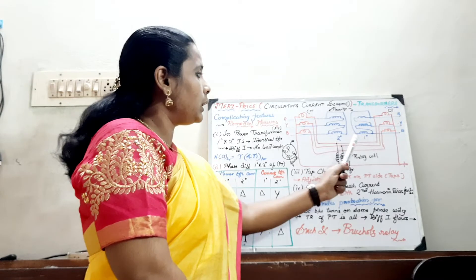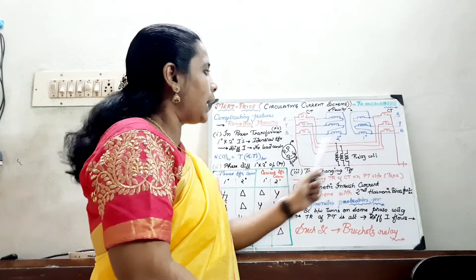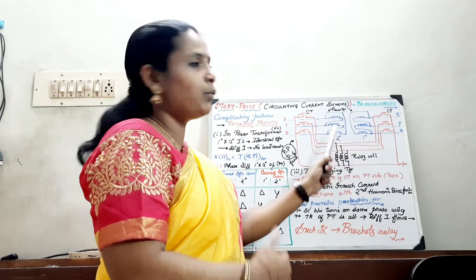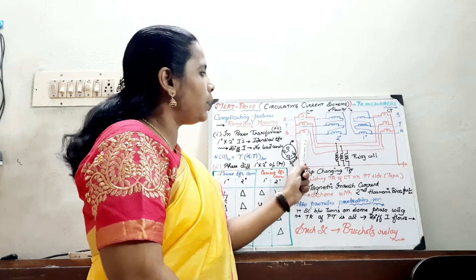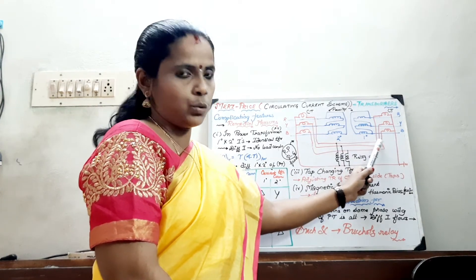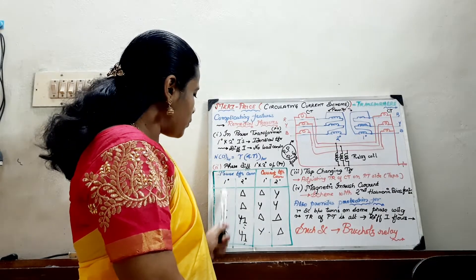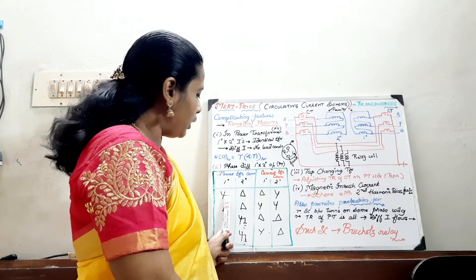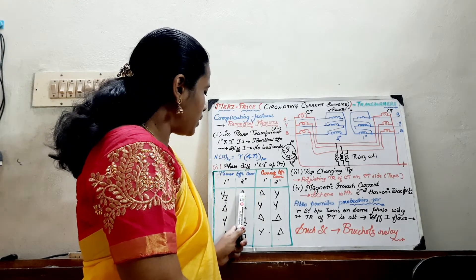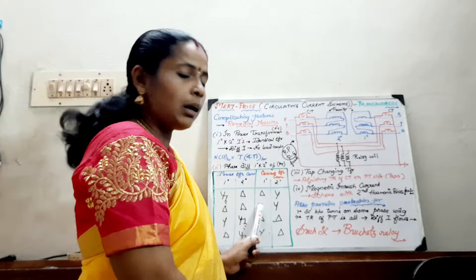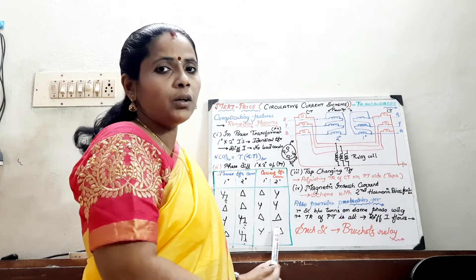The second problem is that between the primary and the secondary of the power transformer, there exists a phase difference. We have seen the magnitude difference first; there is also a possibility of phase difference even if you provide the turns ratio properly. In this case, suitable connections on the CTs must be provided — that is the solution. The power transformer connection determines the CT connection. If the power transformer primary and secondary are star and delta respectively, then the CTs should be connected vice versa — delta and star — to compensate for the phase difference. If the power transformer is star-star, the CTs will be delta-delta; if it is delta-star, the CTs should be star-delta.